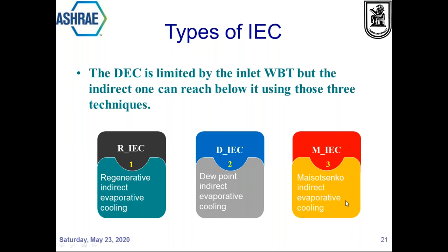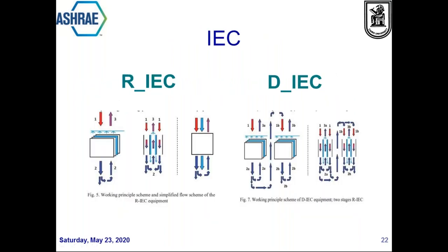Okay. Another question from Mayank Dubey. He wants to ask, should we also include the energy required to cool the inlet water to 21 degrees Celsius or 23 degrees Celsius or 25 degrees Celsius in the EER or COP calculations? Of course, but the natural water from the river is considered to be at 21 or 22 or 23 or 25. So actually, if you take any underground water or river water, then that's the temperature. So you are not cooling it. But of course, if we use the chilled water at 12, this is included.